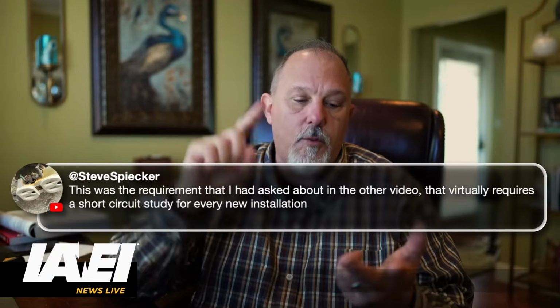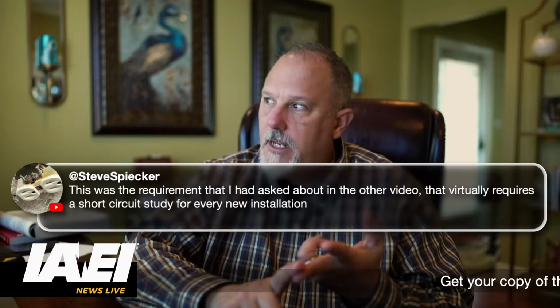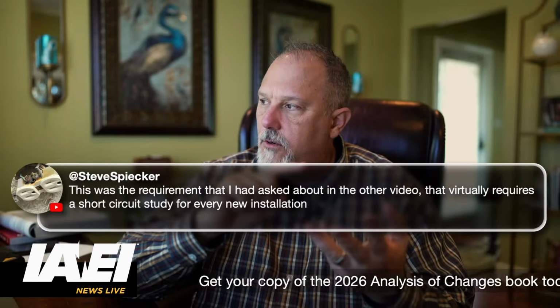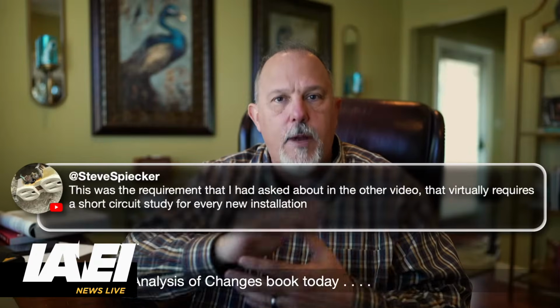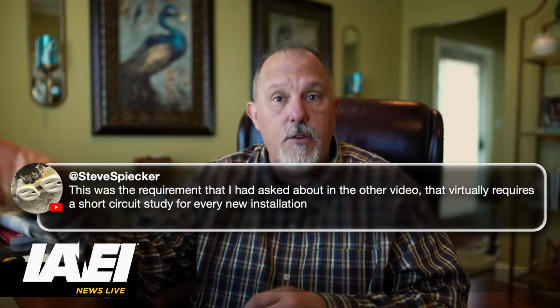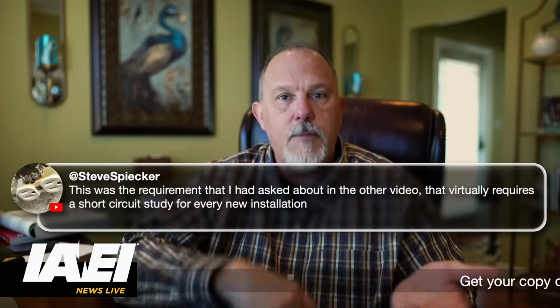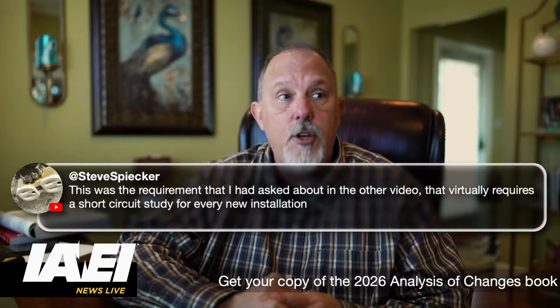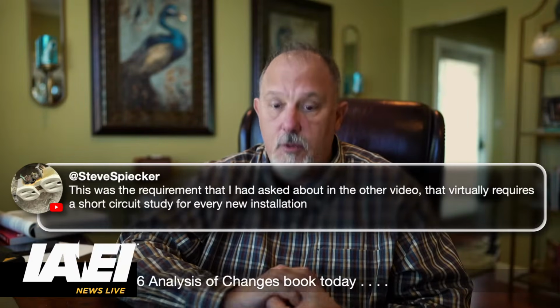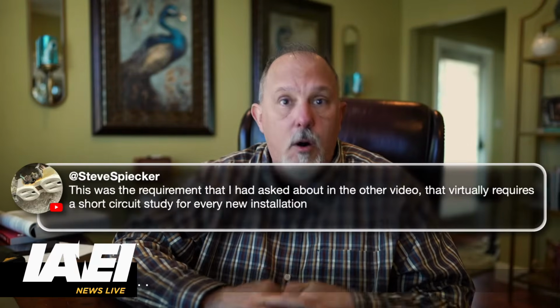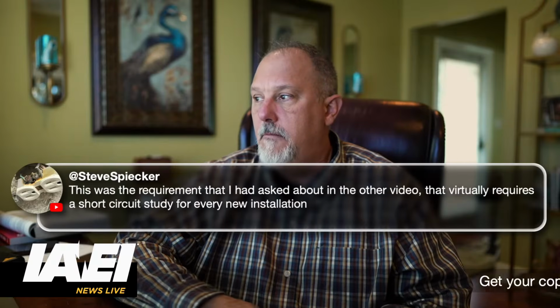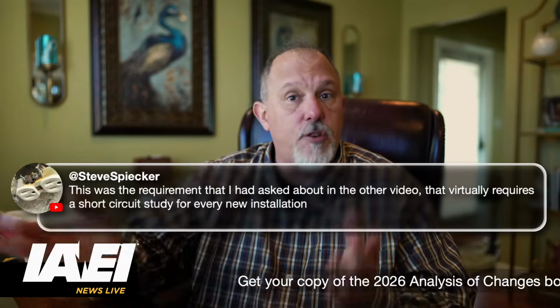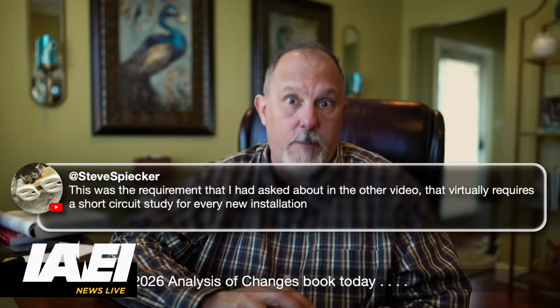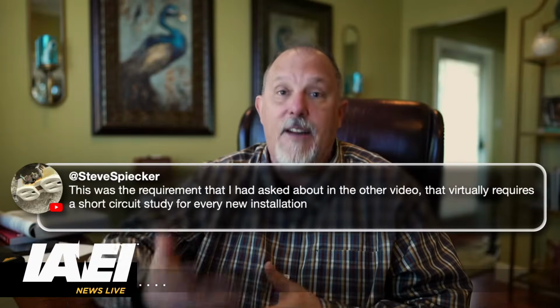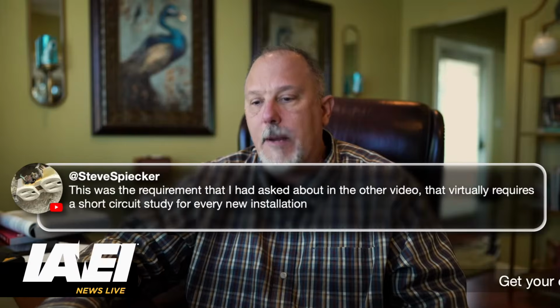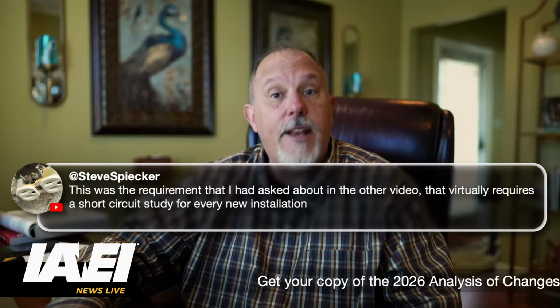I could go to industrial control panels. I can go to elevator control panels. This covers panelboards, switchboards, and switchgear. Multiple areas in the National Electrical Code are now requiring either a field marking, in some cases, and in some cases that calculated value has to be made available. So if I'm in a commercial school, if I'm in a mall, if I'm designing an office, any type of office building, strip mall, I have to do a fault current calculation and I have to label equipment. The arc flash label comes after that. So you probably meant to say an arc flash label, but I just used that as a springboard, Steve.